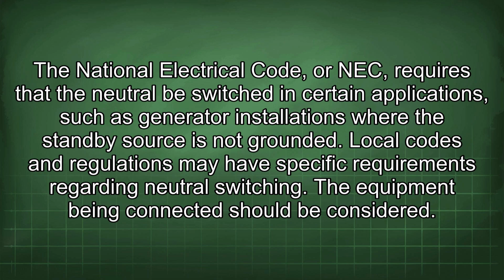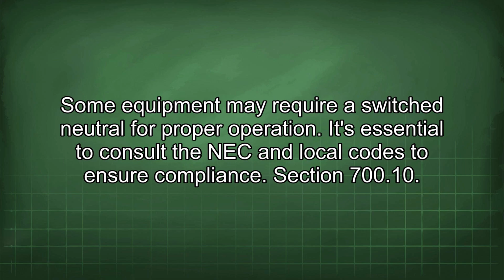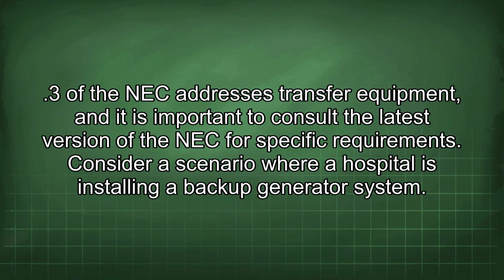The equipment being connected should be considered. Some equipment may require a switched neutral for proper operation. It's essential to consult the NEC and local codes to ensure compliance. Section 700.10.3 of the NEC addresses transfer equipment, and it is important to consult the latest version of the NEC for specific requirements. Consider a scenario where a hospital is installing a backup generator system.